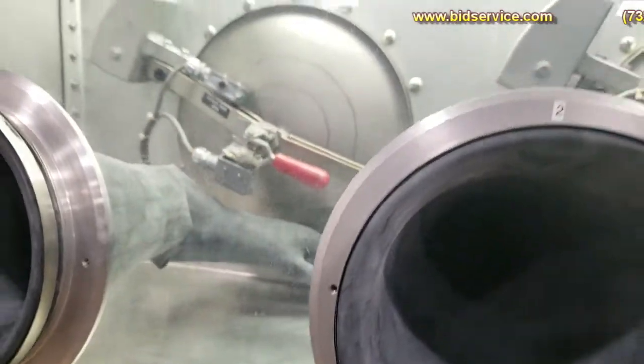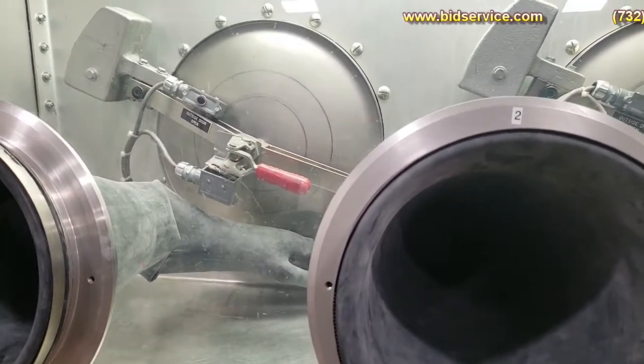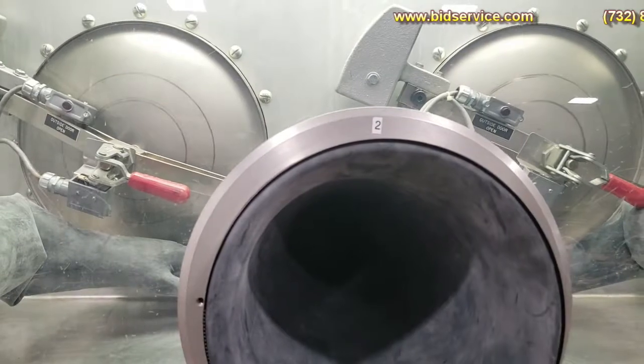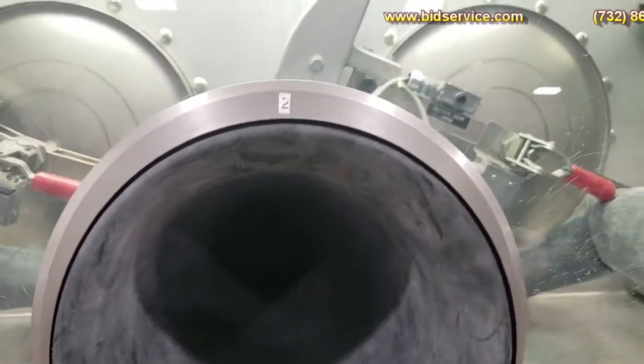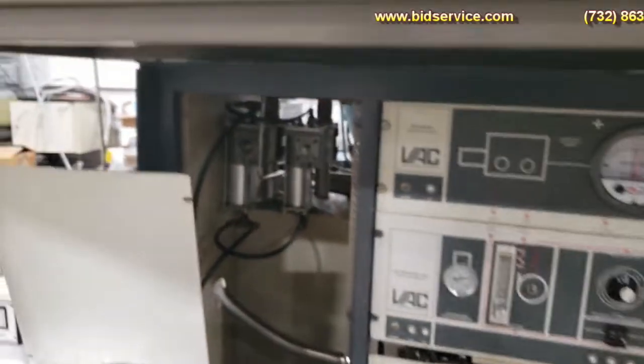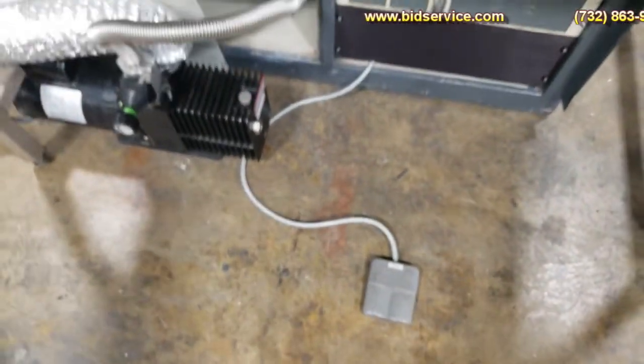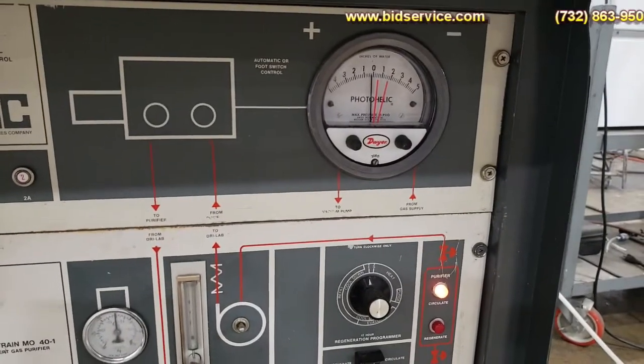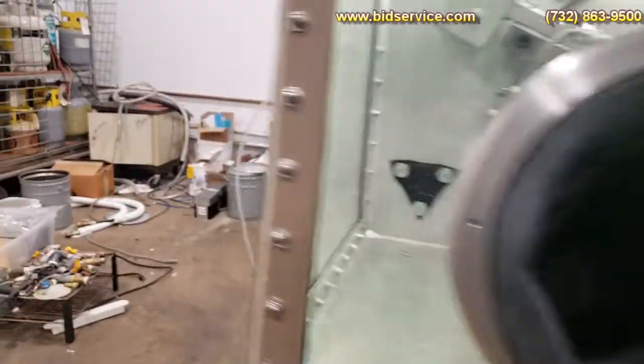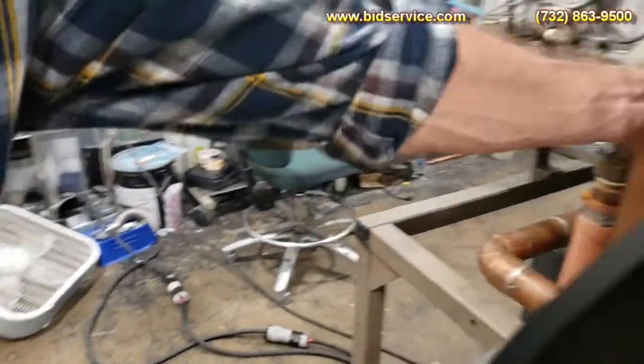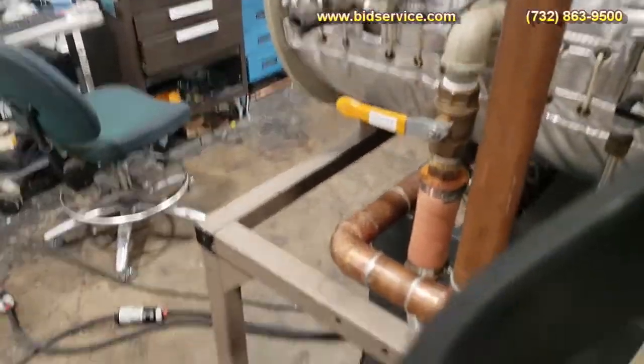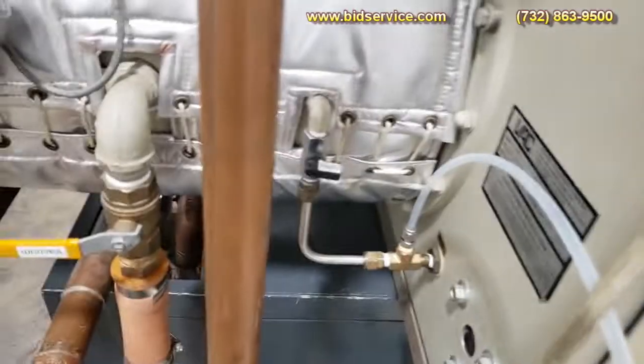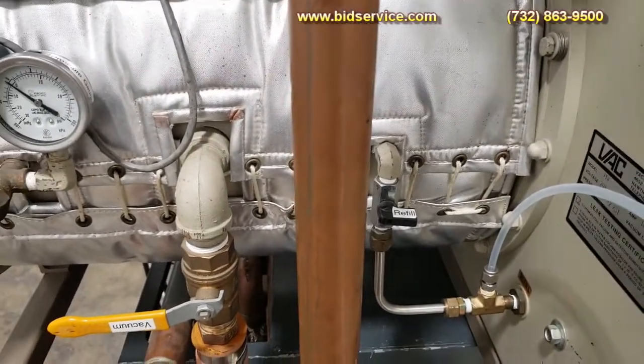Open the antechamber. Now we can open the inside doors first. Typically that's just not going to touch anything because it's still at very high temperature, 150 degrees. So using a foot switch, I'm adding a little pressure to the box. But again, the Photohelic will keep it within the range that you have it set at. Okay, let's come over here, and we'll close this refill valve. I close it by putting it in a horizontal position.